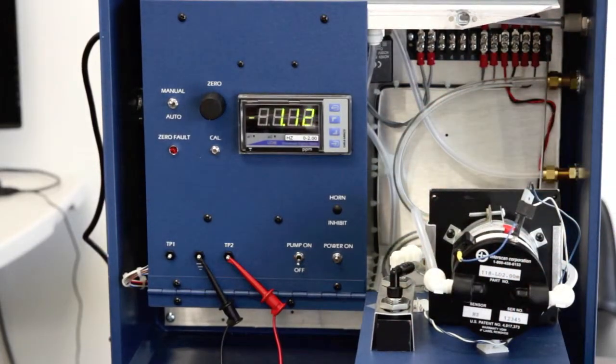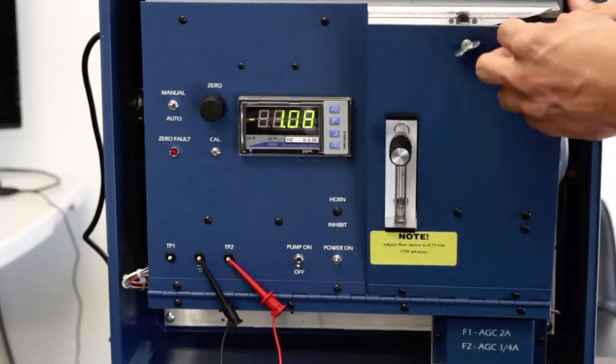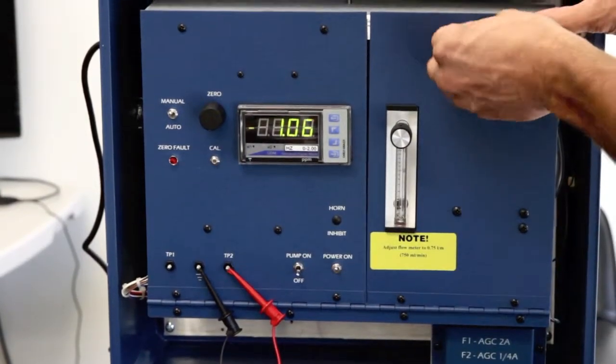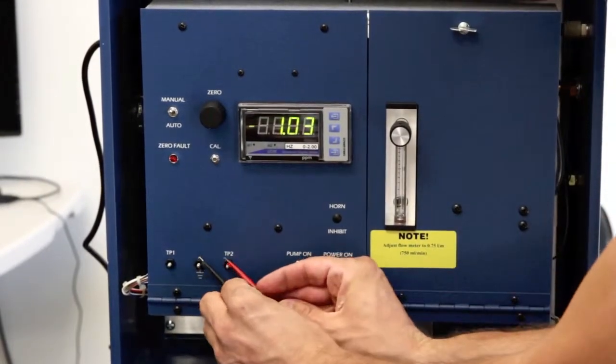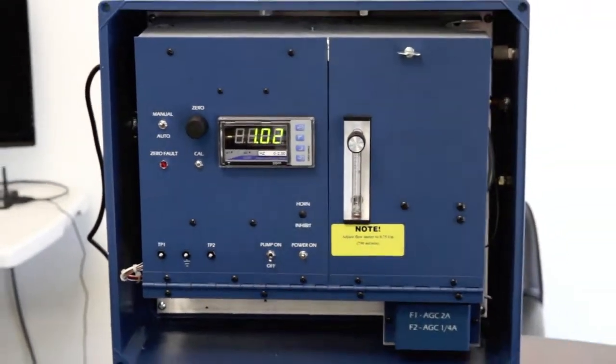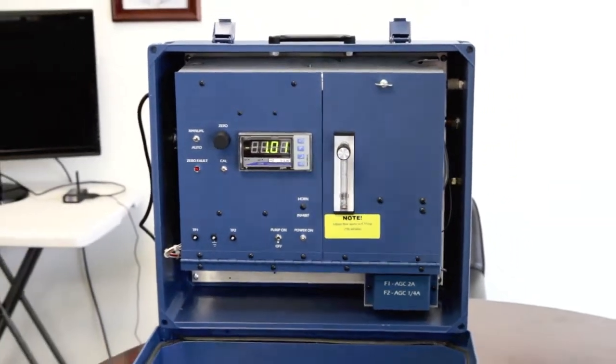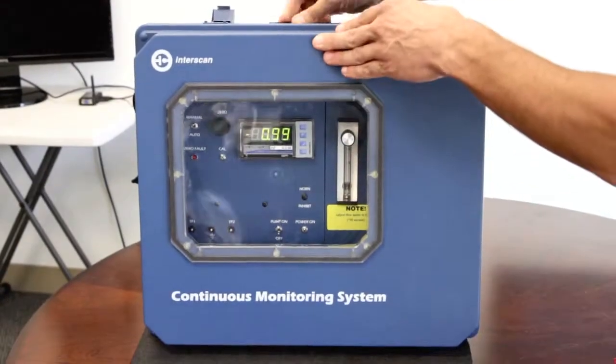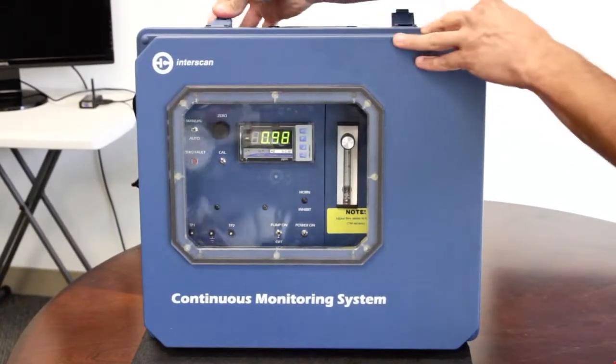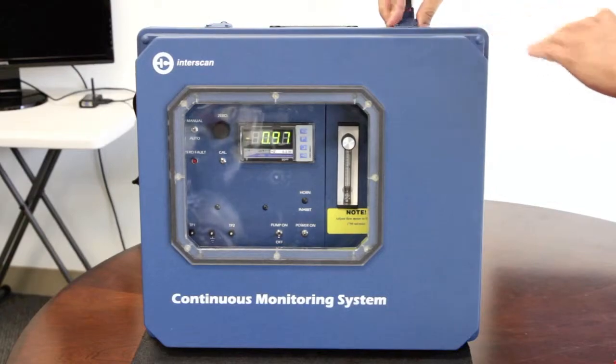The ECS calibration is now complete. However, your analyzer is not ready for use. Please allow 24 hours for the sensor to stabilize. Afterwards, you can begin the zero procedure as documented in your instruction manual and your instrument is ready for use. Thank you.